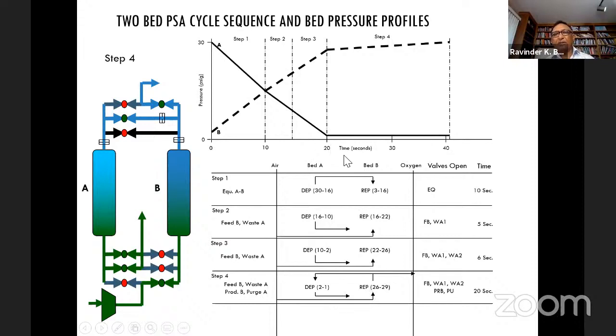At the same time, we are taking part of the oxygen and purging it. You see the purge valve is open, so bed B is purging bed A. This is the longest step, the oxygen production step. In this case, it happens to be 20 seconds.